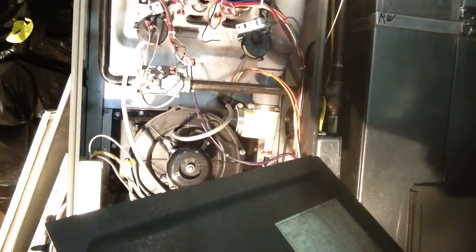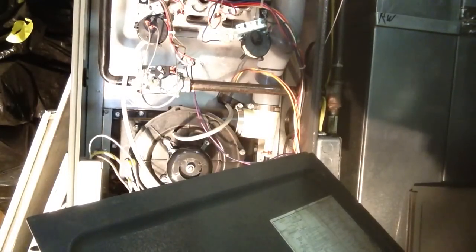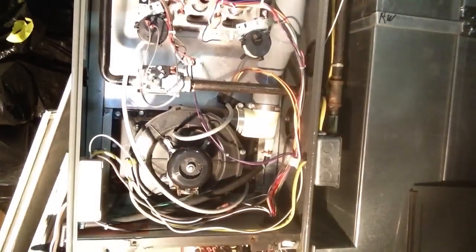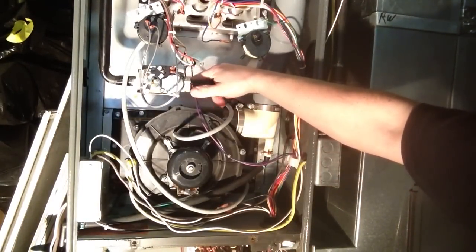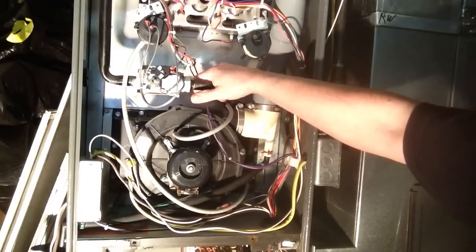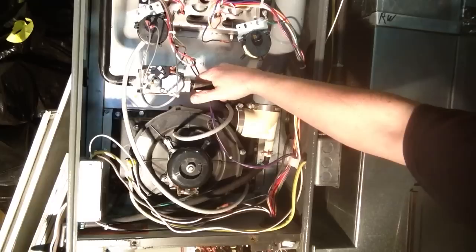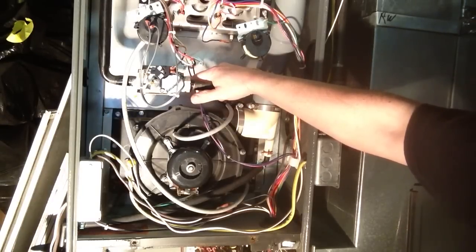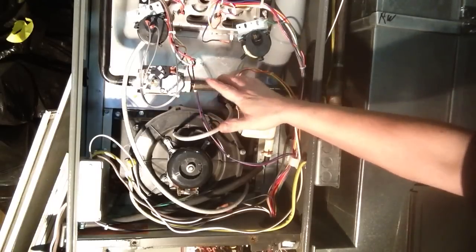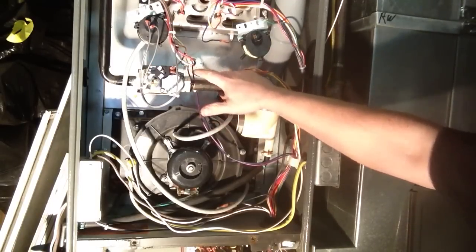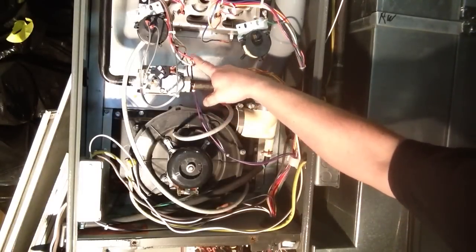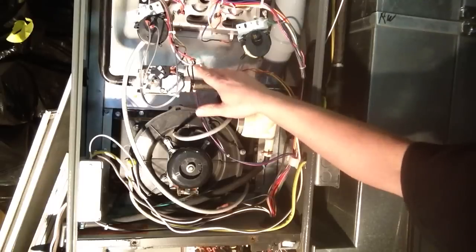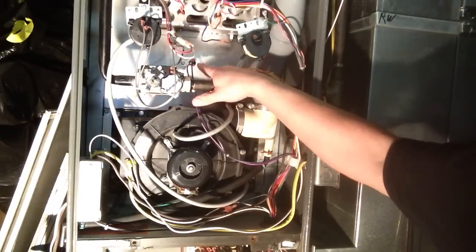Number four is open high limit. That means this limit switch in here opened up and shut the furnace down. Usually a clogged filter, dirty secondary heat exchanger, return air blocked on the first floor, second floor, or a pillow or a blanket over top of it could trip your high limit. That's right in the middle, right here.